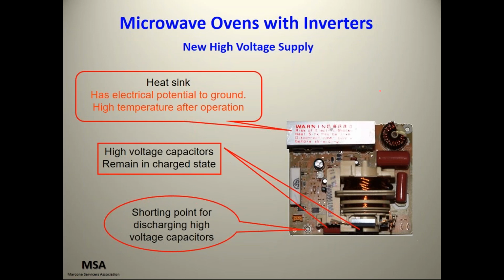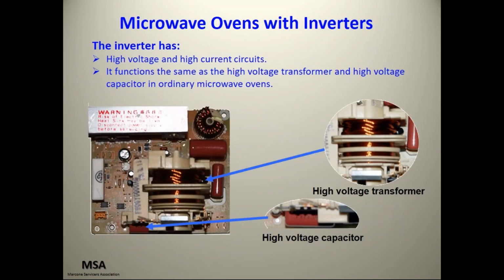Okay, the heat sink, and again, they're fanatical about this thing, these last couple of slides. It has electrical potential to ground, high temperature after operation. There's your high voltage capacitors down here, and that shorting point, which they already mentioned, to discharge the capacitors. Okay, the inverter has high voltage and high current circuits. It functions the same as a high voltage transformer and high voltage capacitors in ordinary microwave ovens. So again, certainly care must be taken if you're anywhere near this board and that machine is operating.